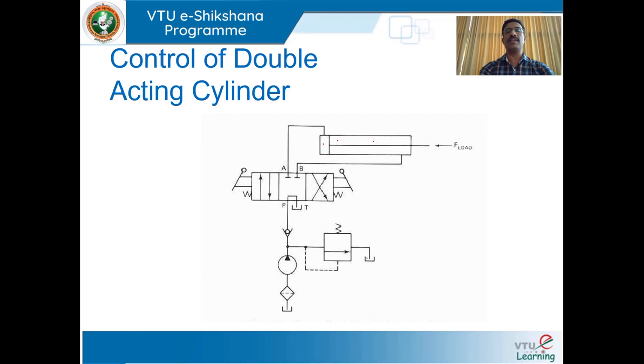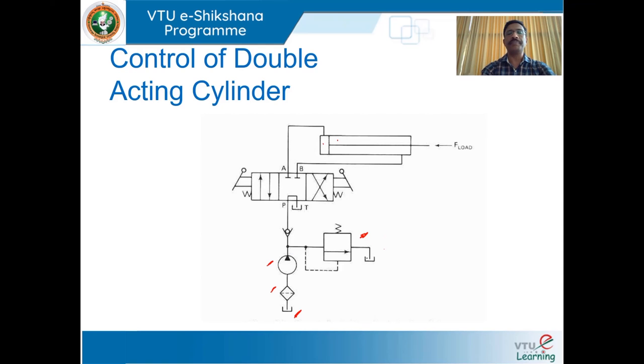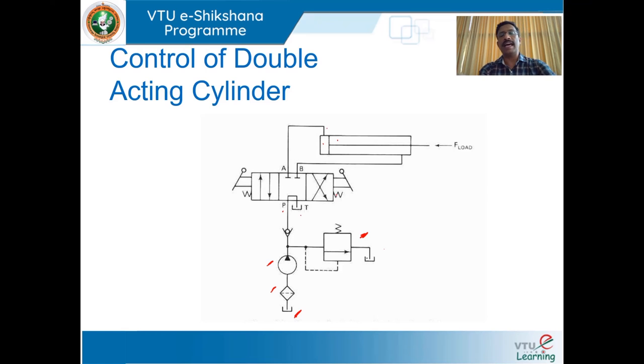The components used to develop a circuit for control of a double acting cylinder are: a tank, a filter which removes contaminants from the oil, a hydraulic pump, a pressure relief valve, and a four-way valve where P is connected to the pump line, T is connected to the tank line, A is connected to the blank end of the cylinder, and B is connected to the rod end. Three squares are used for the three-position directional control valve — this is a manually actuated spring-centered type.